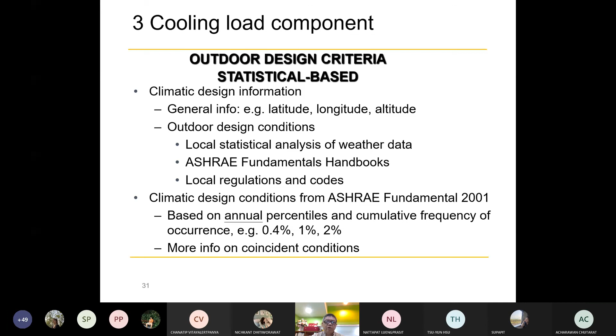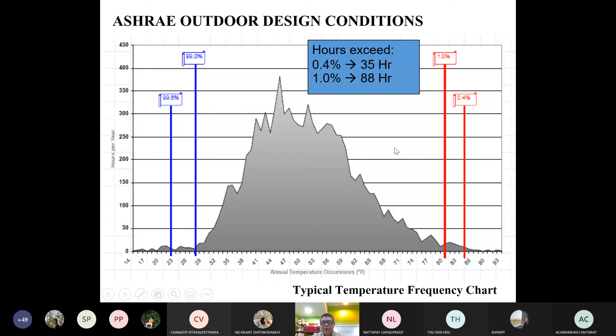They show how many hours of the year have a certain temperature. For Thailand, the graph will trend more to the right-hand side. For cooling load, you can see the temperature used - maybe 0.4% for the highest temperature in Thailand, like Bangkok's 37 degrees. But for load calculation, we normally use the 1% value, meaning dry bulb.